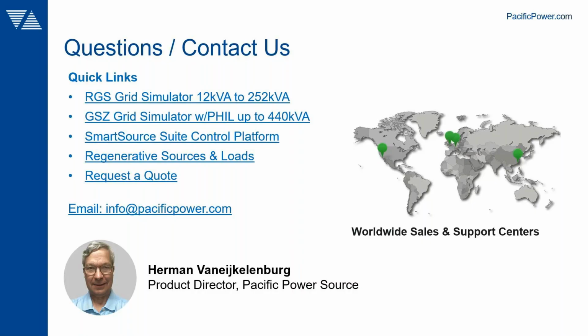Is it possible to use the grid simulator mode and electronic load mode at the same time on a single unit? It is, in mixed mode. If you're in three-phase, split phase, or single phase mode, all three outputs are synchronized, as you'd expect for a grid simulator or AC source. If you use independent channel modes, where channels are isolated, you can have different modes on each channel. So one or two channels can be source, and the third can be set to load. As shown earlier, you drive the UUT input side with one or two phases, and on the output hook up the third channel in load mode, AC or DC, to absorb energy from the output of the same UUT.